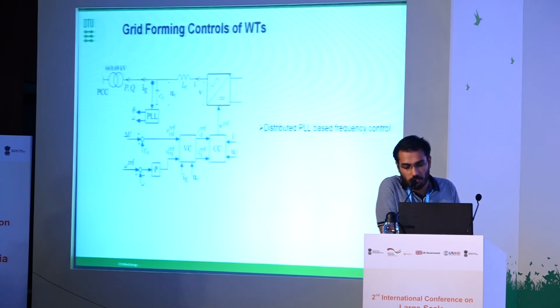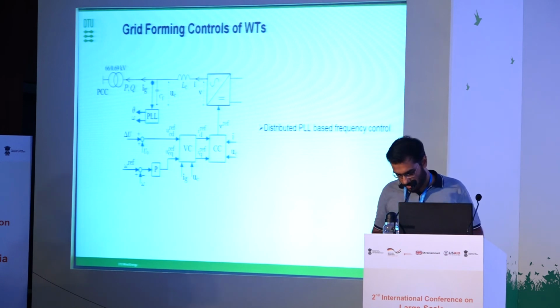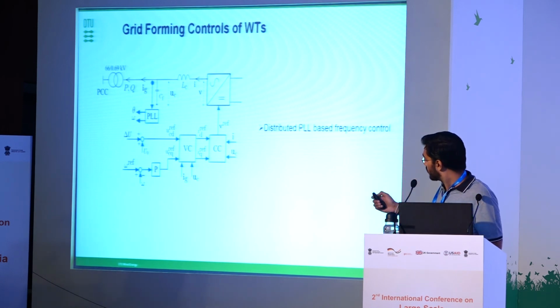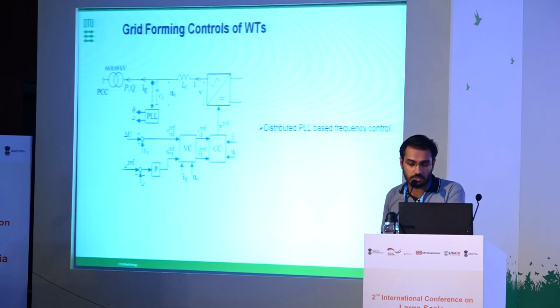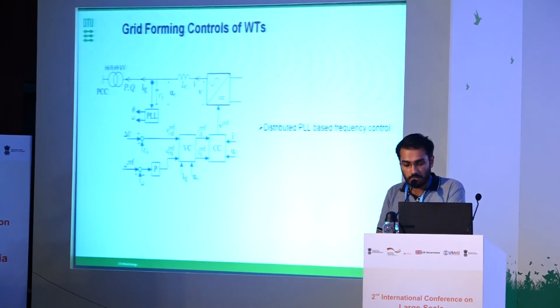So this is, for example, one grid forming control. I will not go into the technical details, but essentially, instead of controlling the voltage source converter as a current source, you control it as a voltage source with a voltage and frequency reference. There exist different grid forming controls, and it is just a control matter. There is no special change required on the converter end.